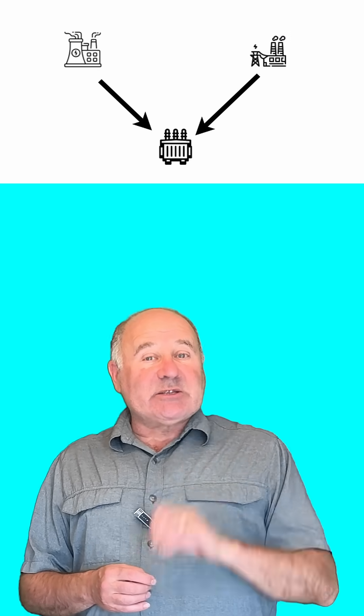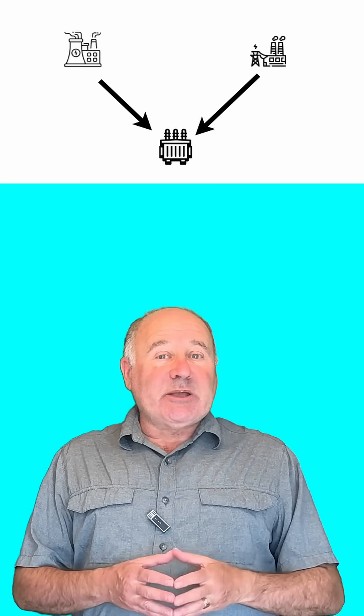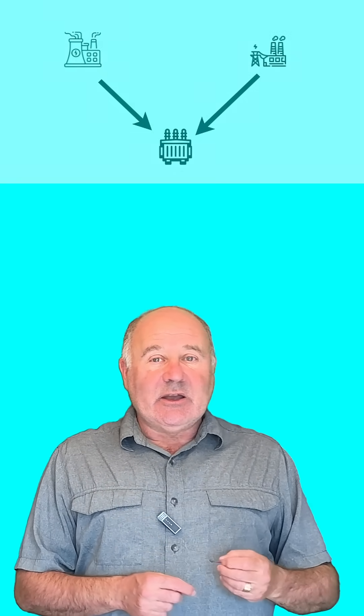In a healthy grid, the current should be flowing from generators to substations, and from there to places where the electricity is needed. There should be no current flowing from generator to generator. For that to happen, every generator at every moment has to be operating at the same voltage. If not, we'll see currents from one generator to another.